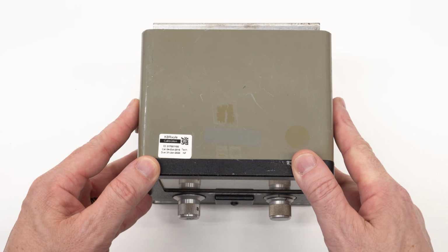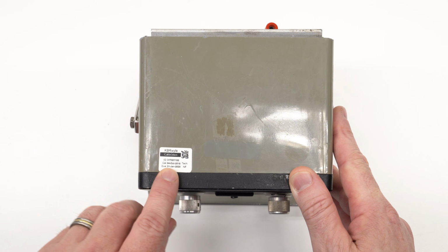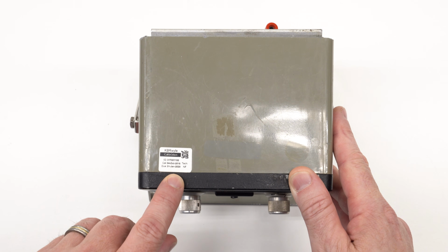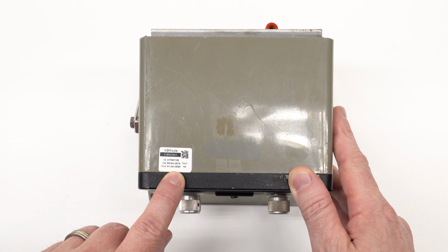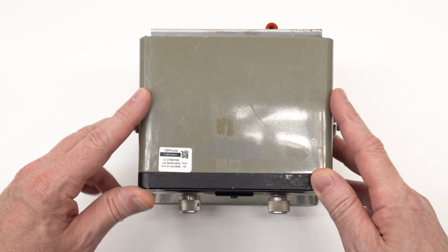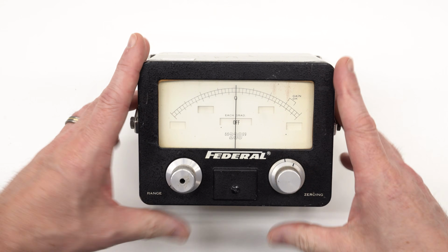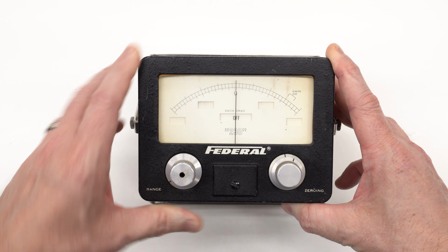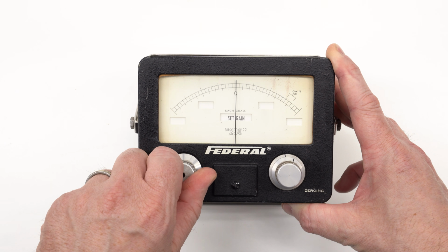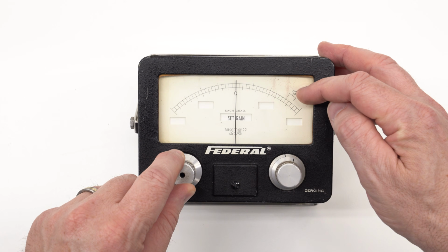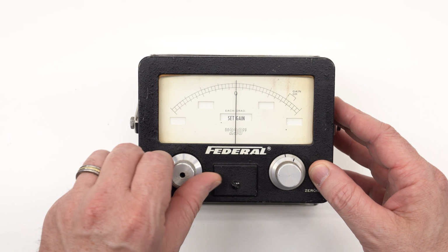There is a calibration sticker here on top. Looks like it was last calibrated in October of 2018, due again in January of 2020. So that's a pretty recent calibration. This must have been in use until just recently. Dial looks nice and clean. Let's turn it on. And yeah, no response from the set gain. So if there's a battery in it, the battery is dead.